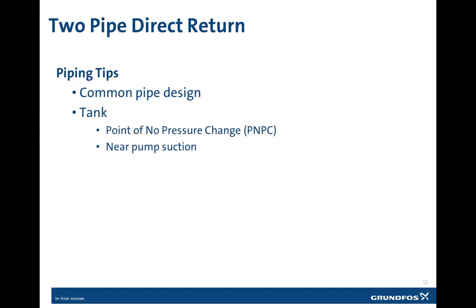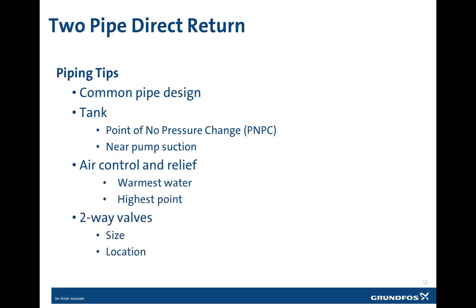Now, when designing a two-pipe direct return system, there are three things that need to be considered, so some of the piping tips involved. The first is that it does use a proper common pipe design. And then it has one tank that's located at the point of no pressure change, also for the warmest water. And then it utilizes air control as well as air relief for the system, for the warmest water for the application, and also the highest point in the system. And then it utilizes two-way valves that are located downstream of the coils. And we'll talk about some of these details a little bit later in this section.